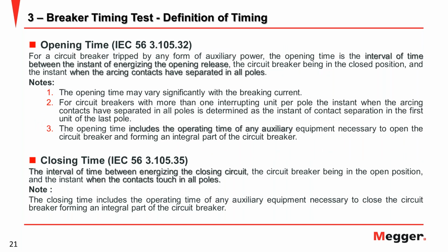The opening time is the interval of time between the instant of energizing the opening release, so when the coil gets the voltage for the first time, and up to when the arcing contacts have separated in all poles. If only one has separated, the last time will be used as the opening time. So from here, very clearly, the opening time is calculated from when the coil is energized up to the arcing contact separation. The closing time is the same but with the opposite definition.